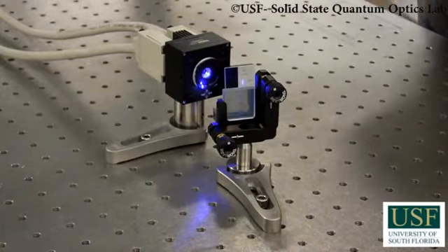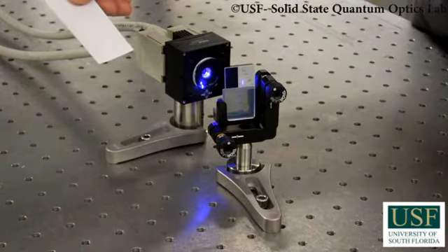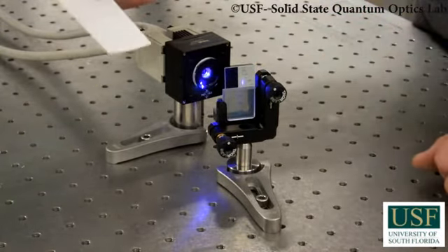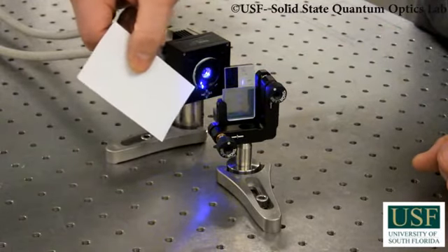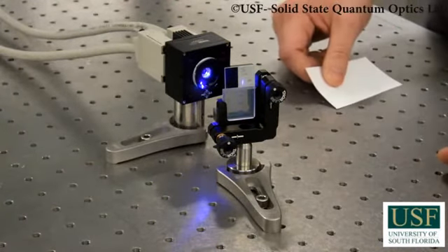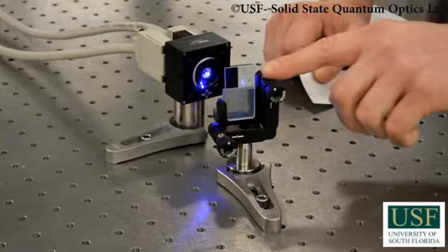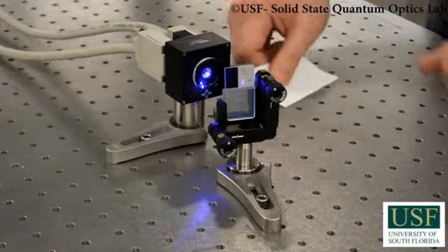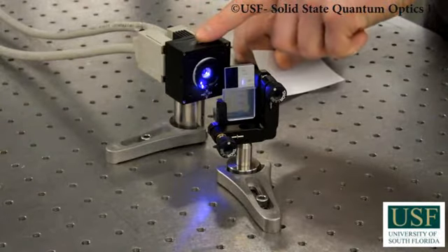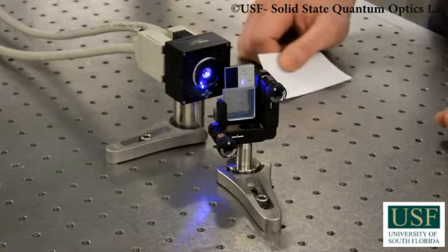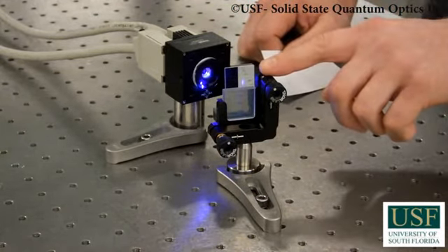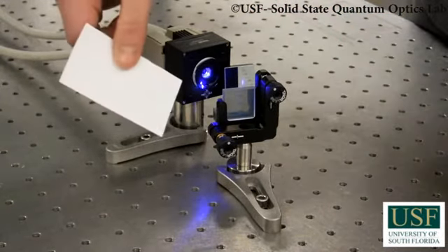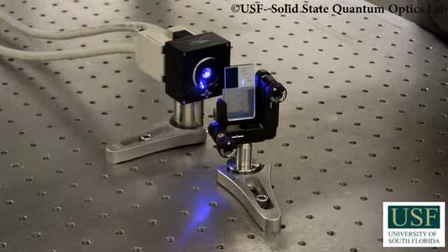The first step in the first part is to locate the first order maxima. In our case, the diffraction grating is highly misaligned. Therefore, the first order maxima is easily located. But it may be the case that the diffraction grating is only slightly misaligned. In this case, the first order maxima will be indistinguishable from the beam exiting the laser diode. To solve this, you can purposefully misalign the diffraction grating within the tolerances of your system such that you can easily identify the first order maxima.